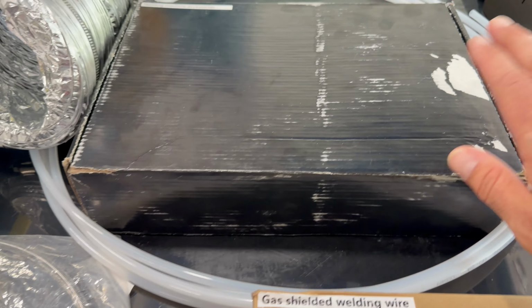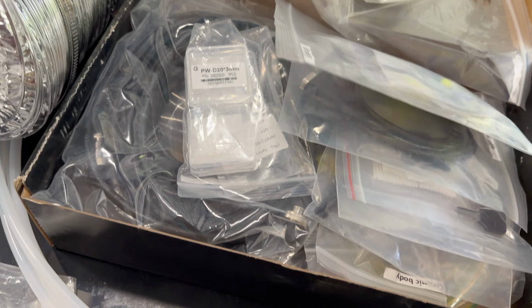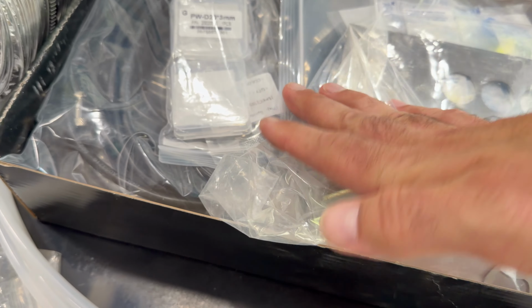In this box here we've got all the welding machine accessories, and there's a lot of parts and pieces. We've got some sample cuts, earplugs for safety, a USB communication cable, additional communication cables, power cable for the welder, our different lenses, cleaning parts and pieces, an extra ceramic body, optic caps, more air tubing connections, a grounding wire, and grounding clamp. So that's all in this main box.